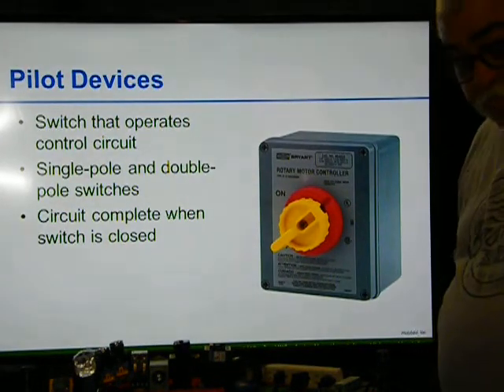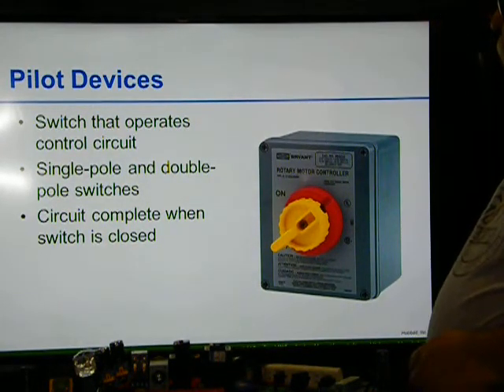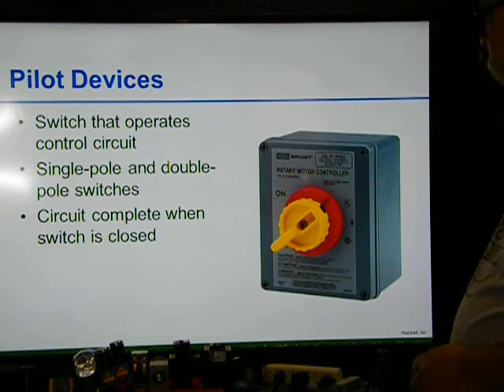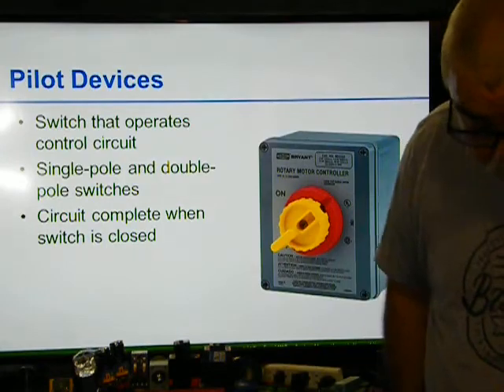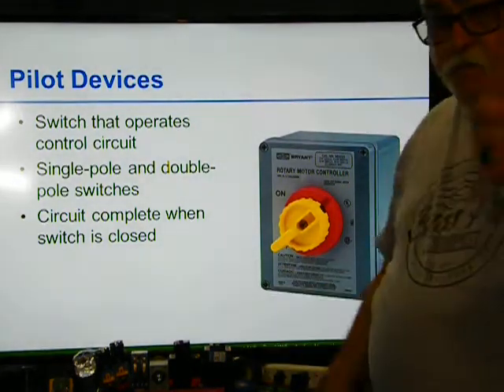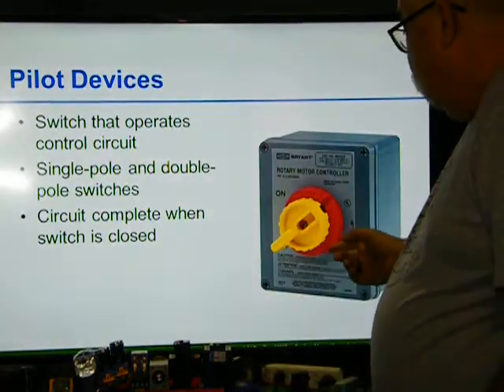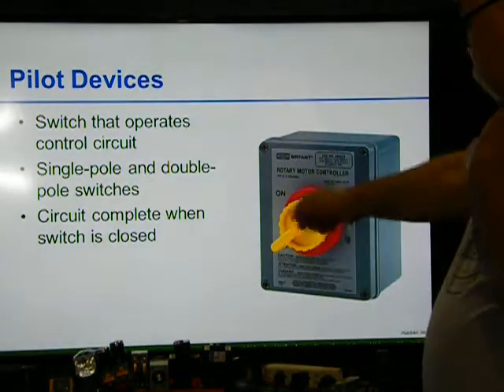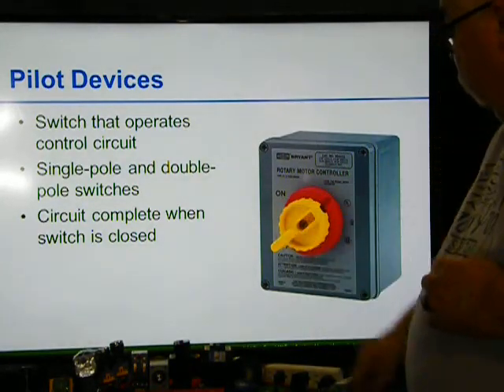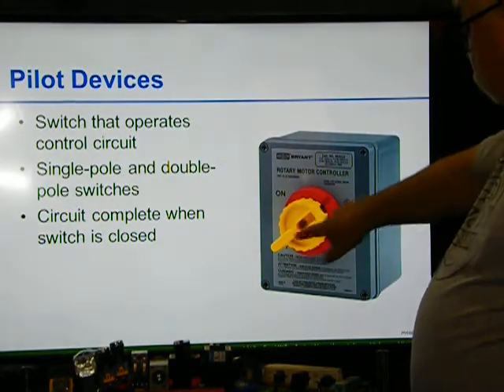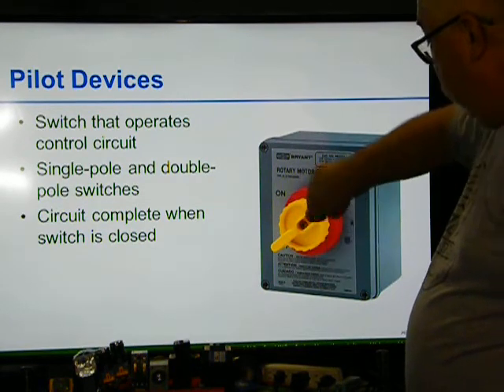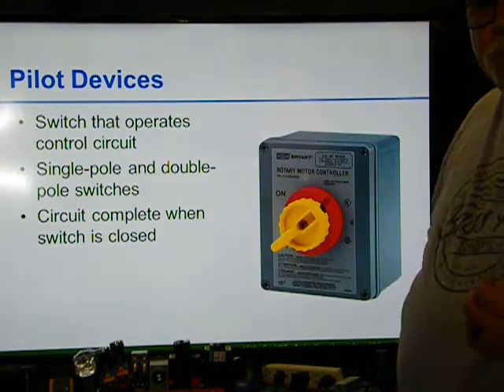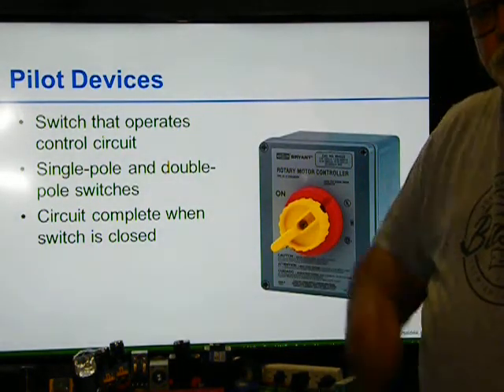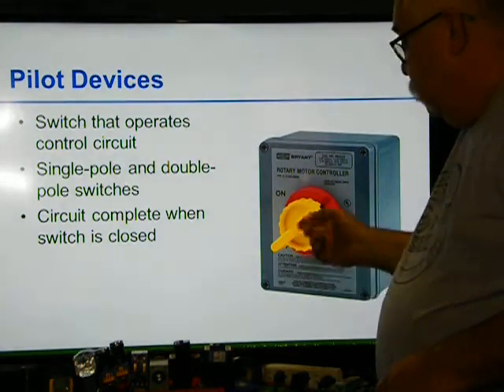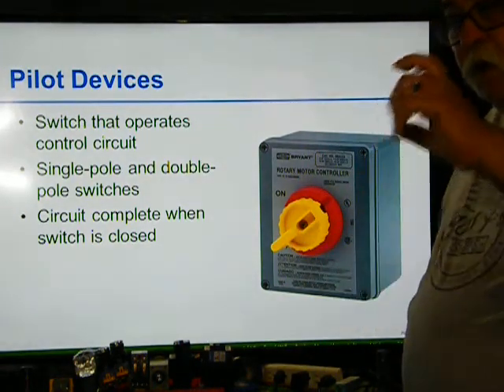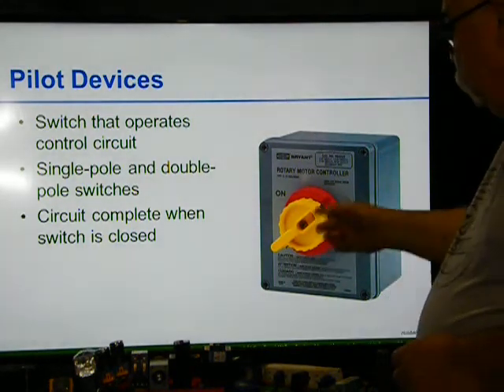Pilot devices. Switch that operates control circuits, single pole and double pole switches. So when you have a circuit, you can have on and off switch. You can have a motor controller. Still has on and off. There's my off, there's my on. Okay, these allow you to get it right. That there is off. Now you see how it has this groove. Now I can get a padlock, lock it out so nobody can turn it on. So that's what this helps compared to a switch. This one does have a means so you can lock it out. They do make a lockout for switches. This one makes it easy.